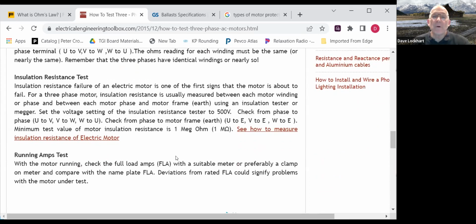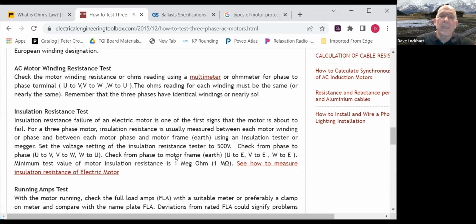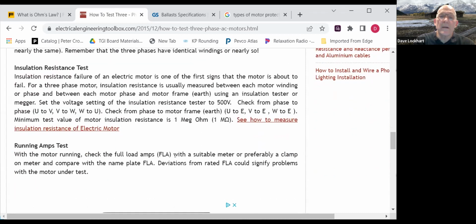I don't know if many people have used a megger before, but a megger checks that all the wires in our motor, which have very thin insulation, are kept separated from each other and from ground. You can take a megger, which creates high voltage. The ones out now are probably push button, but the one I'm most familiar with is a little hand crank. You just crank away, set at 500 volts, connect it to two phases and crank away to make sure you have some insulation resistance between your phases as well as to ground. So the insulation resistance test is done with a megger. The other tests I talked about were just done with a multimeter.